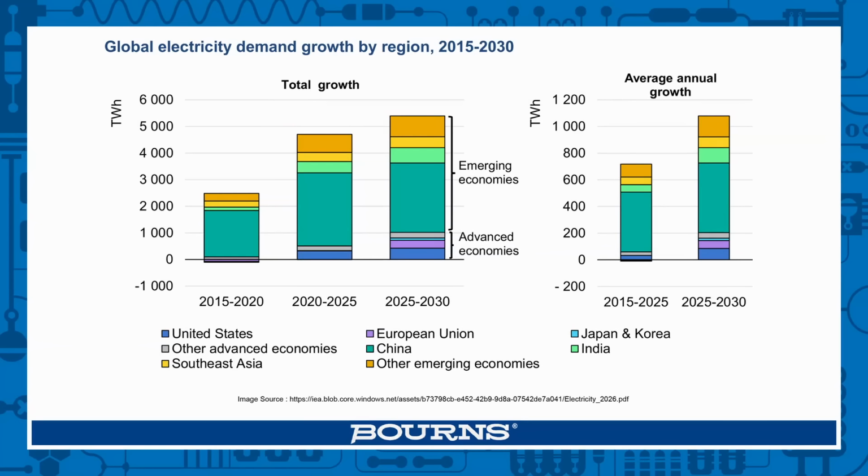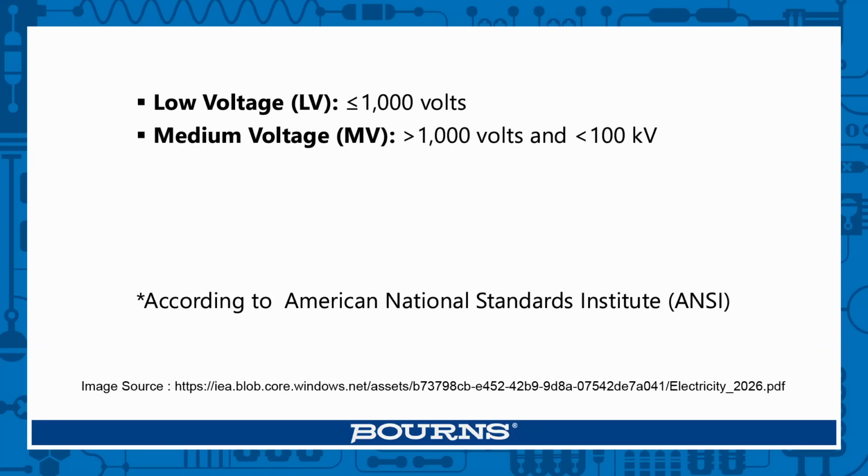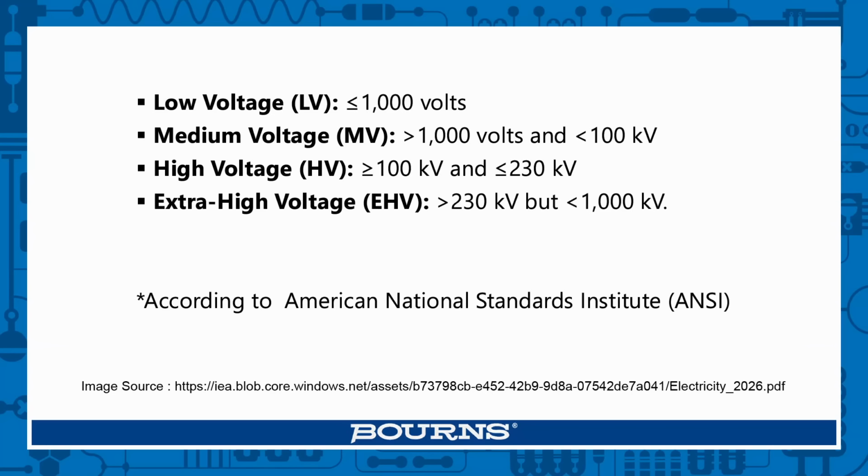Thanks, Stuart. Very good question. Over the past couple of years, we are seeing the demand for energy from the grid increase quite a lot, most notably for artificial intelligence infrastructure. Because copper costs a lot of money, and if you're increasing the amount of power going through the copper, you have to come up with a way of reducing the amount of copper. So what we are seeing happening is, first of all, the voltages are increasing. That helps reduce the amount of copper and deliver high amounts of power.